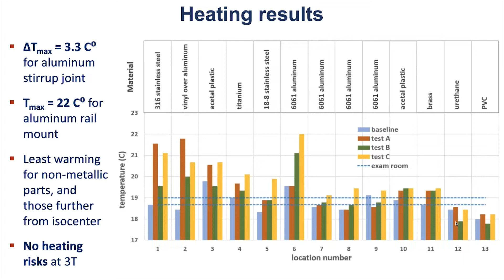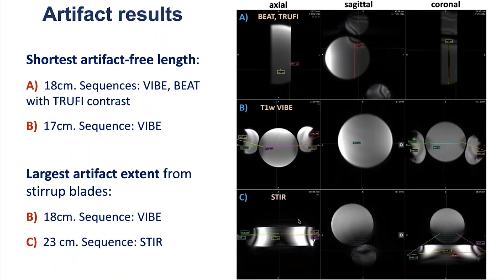The results of the artifact tests are shown here. The shortest artifact-free length measured for test A was 18 centimeters on VIBE and BEAT sequences with TRUFI contrast. And for test B, it was 17 centimeters for VIBE sequences. The largest artifact extent from the stirrup blades was 18 centimeters for the VIBE sequence on test B and 23 centimeters for a STIR sequence on test C.